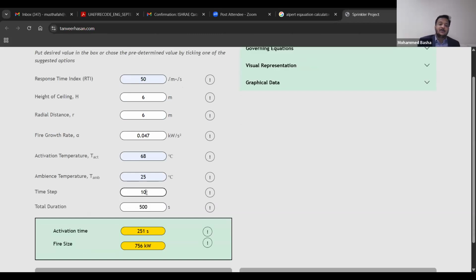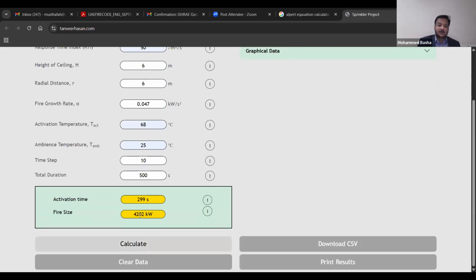Time step. You know what this time step is? It's required in a quasi-steady state or t-squared growth, because at every second the fire growth is different. So I am telling the software to count for every 10 seconds what is happening, and to check for 500 seconds where the activation happens. So I just click calculate. I can see here it is activating at 299 seconds, at 68 degrees, and the fire size at that time will be 4,202 kilowatt.